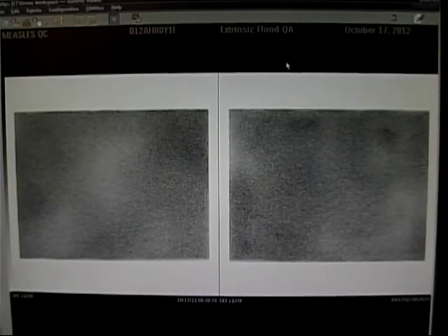So with the lower energy, it will attenuate more and it will show more defects. Now here we have no defects, so this is just how a healthy camera image would look, acquiring a low off-peak image.